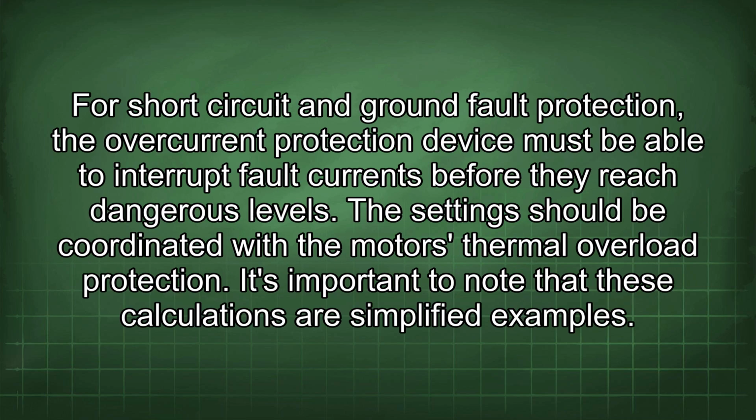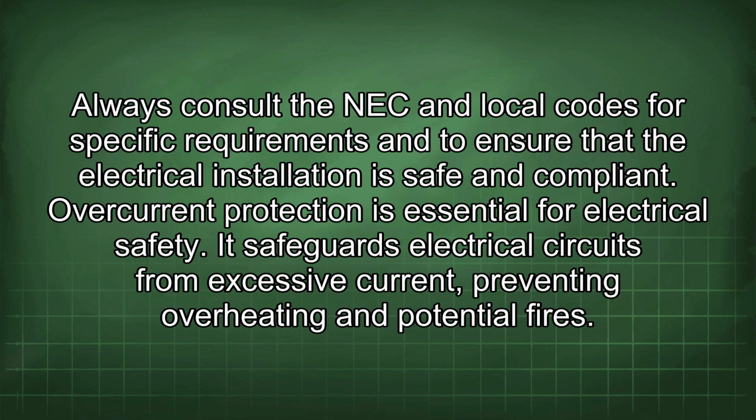For short circuit and ground fault protection, the overcurrent protection device must be able to interrupt fault currents before they reach dangerous levels. The settings should be coordinated with the motor's thermal overload protection. It's important to note that these calculations are simplified examples. Always consult the NEC and local codes for specific requirements and to ensure that the electrical installation is safe and compliant. Overcurrent protection is essential for electrical safety.